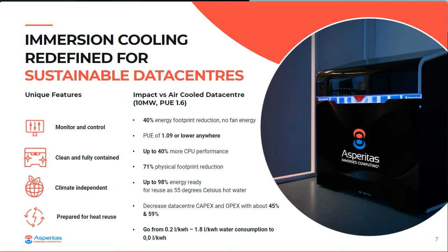There are a lot more benefits. They all relate to energy efficiency and therefore cost and sustainable impact. Depending on the use case, you can provide more optimal CPU performance. If the goal is to apply as much compute power as possible in a limited footprint, immersion cooling can provide that as well. In Europe there is a lot of attention for heat reuse scenarios, and this is definitely feasible. The temperature should be higher, and the cooling medium — in this case water — is a lot easier and more efficient to transport with a lot less losses compared to air.